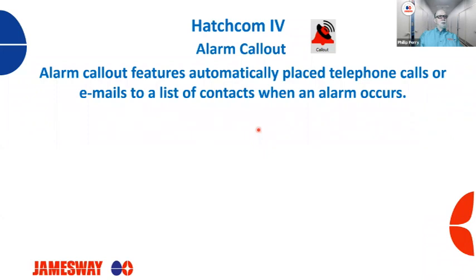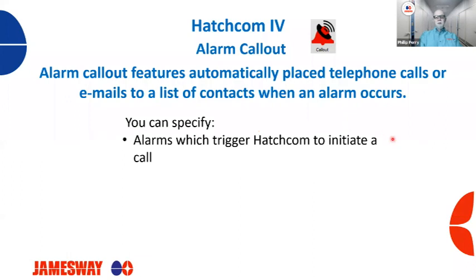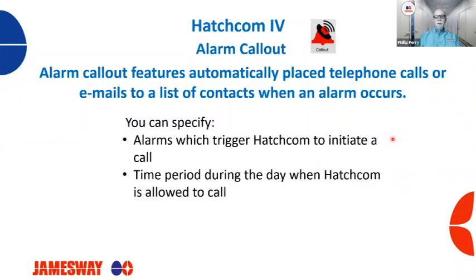The alarm call out feature automatically places phone calls or emails to a list of contacts when an alarm occurs. You can specify alarms which trigger Hatchcom to initiate a call. You can set the time period during the day when Hatchcom is allowed to call. So if you're working at the hatchery and you're the primary alarm contact, then you may want to disconnect it so it's not calling you or bothering you throughout the day when you're at the hatchery. Again, you can specify this now.